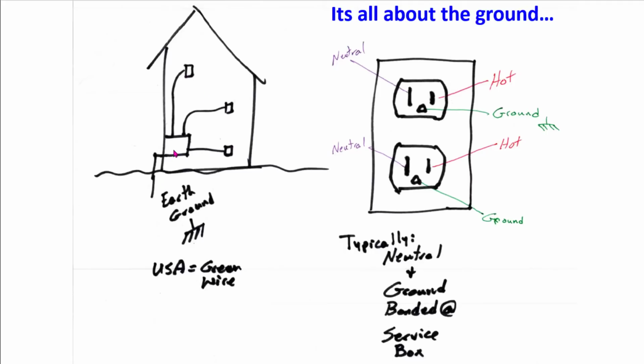And then typically coming out of this box, there's a ground bus in it. And that ground bus is tied outside into a copper rod driven, typically a zinc-coated copper rod, 6 feet into the ground or so outside your house. So it truly is ground. It's driven into what's called earth ground. And typically this earth ground is tied back in here. And here in the US, it is the green wire, okay? If you're working inside of something and you see a green wire, it's typically tied all the way back here to earth ground through these outlets, okay? So these are what your outlets might look like on the wall, and you got 3 prongs here in the USA, okay? One is ground, earth ground.